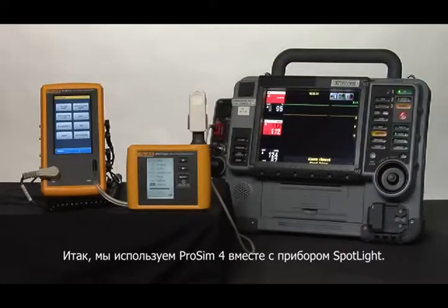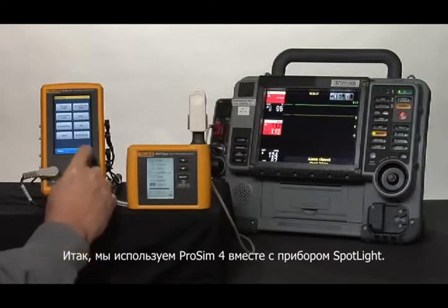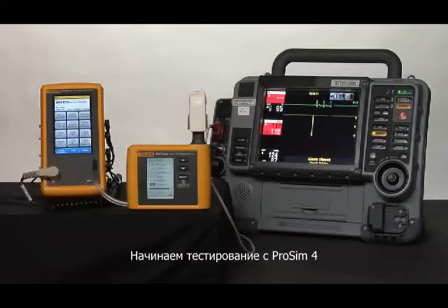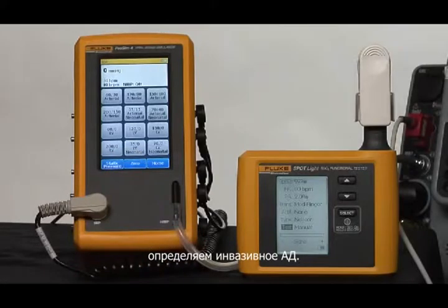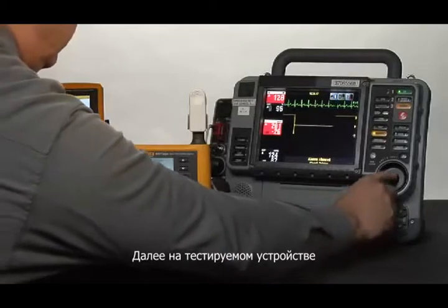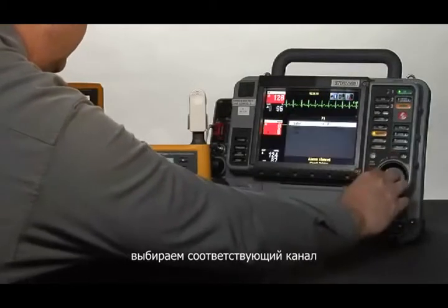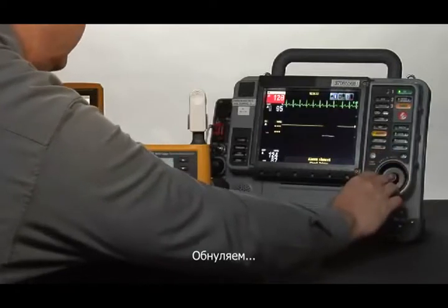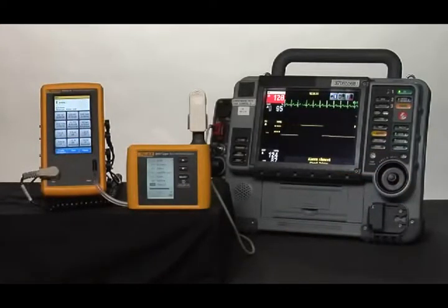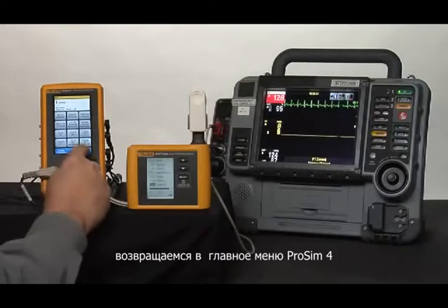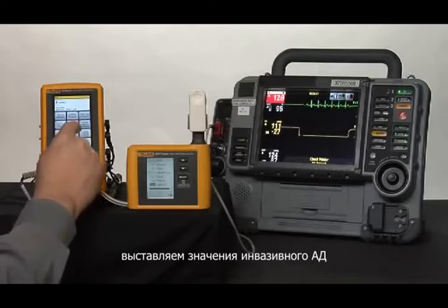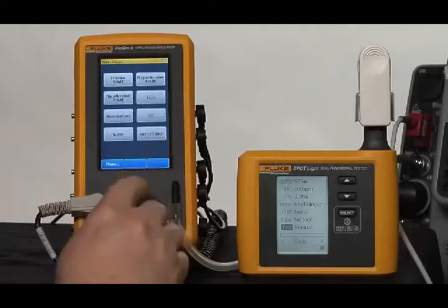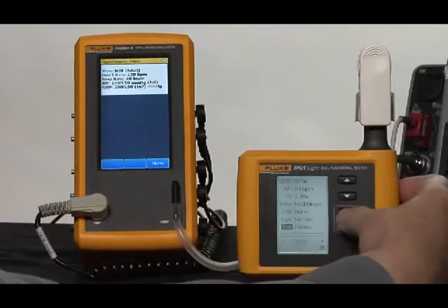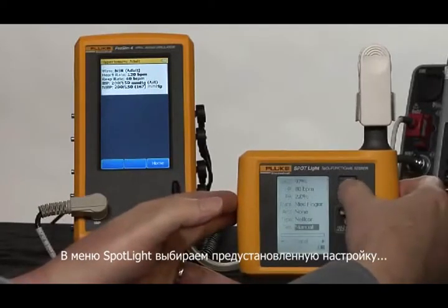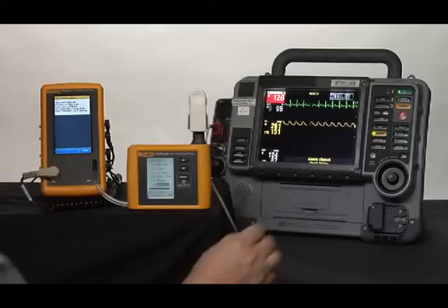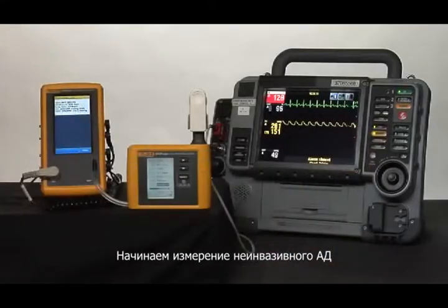We'll pick both our ProSim 4 and our Spotlight, and I will go on ProSim 4 first to IBP and 0, and then on the clinical device I will select my channel in 0, the IBP channel. As soon as I have a 0, I can go on ProSim 4 back to the home screen, hypertensive patient. On the Spotlight, I want to pick custom 3, and I want to start an NIBP reading on the patient monitor.